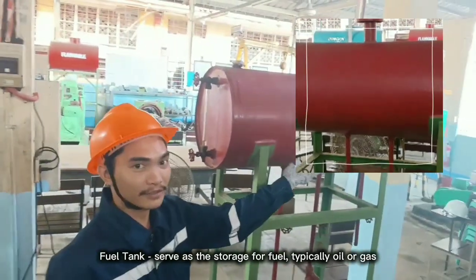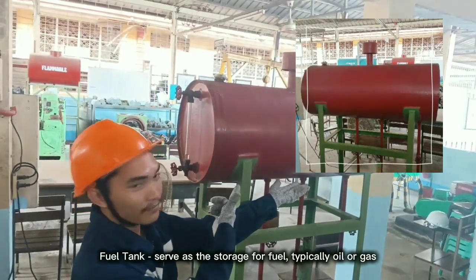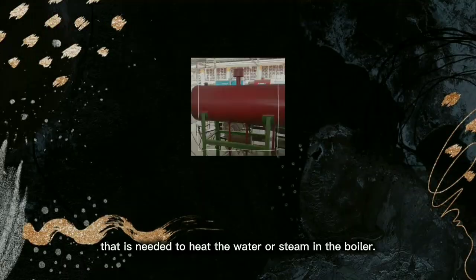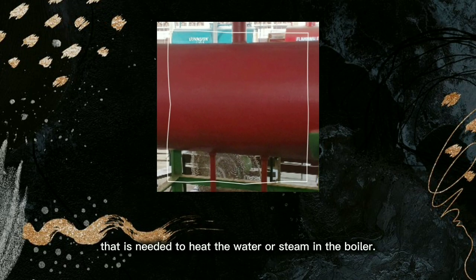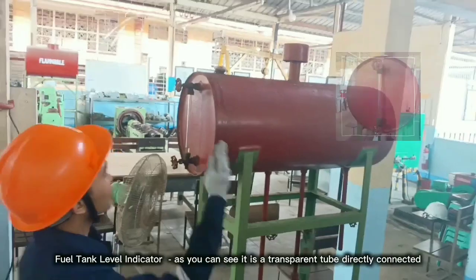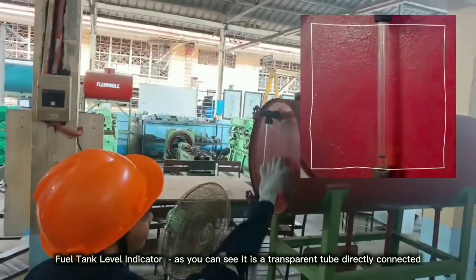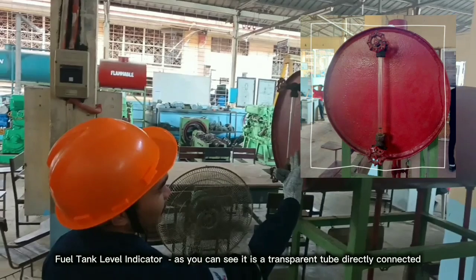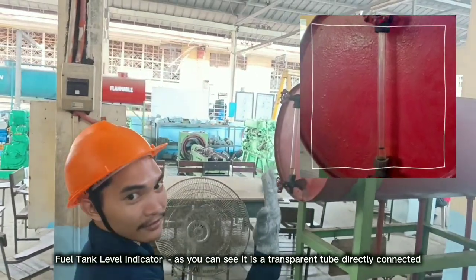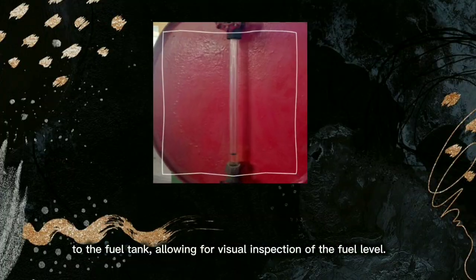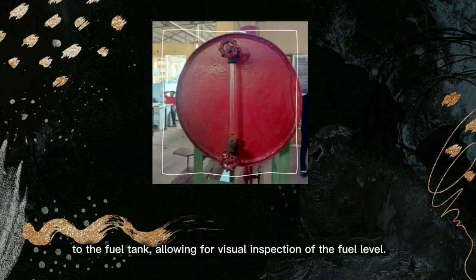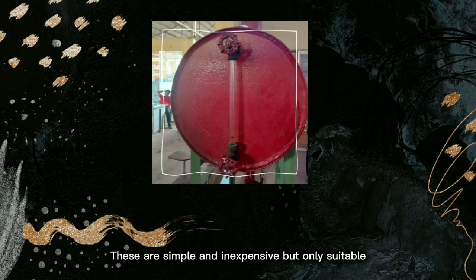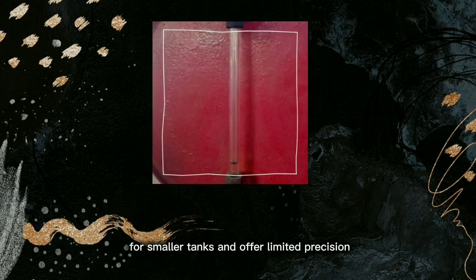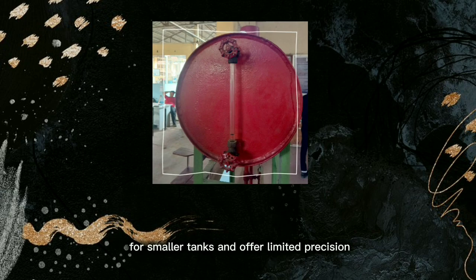Fuel tank. It serves as storage for fuel, typically oil or gas, that is needed to heat the water or steam in the boiler. Fuel tank level indicator. As you can see, it is a transparent tube directly connected to the tank, allowing for visual inspection of the fuel level. These are simple and inexpensive but only suitable for smaller tanks and offer limited precision.